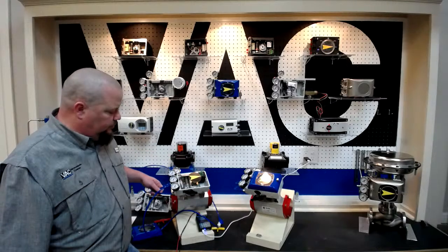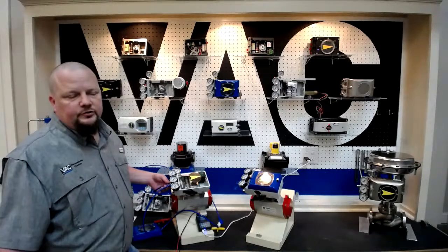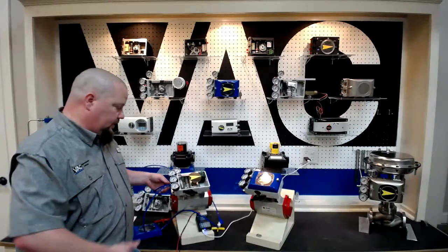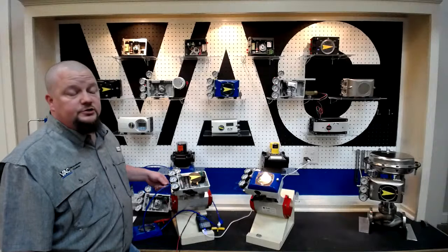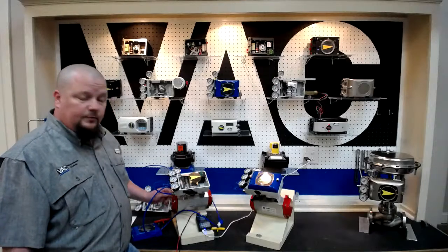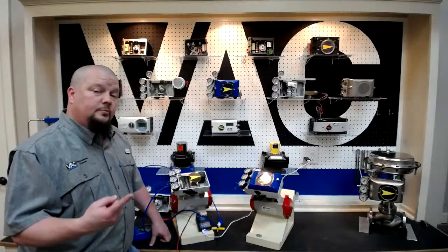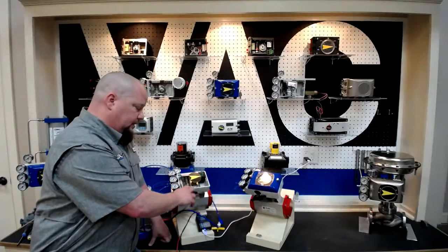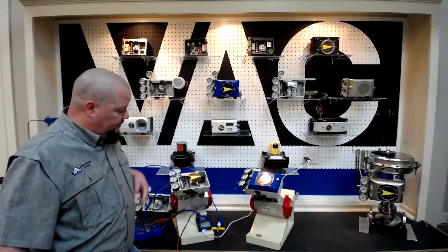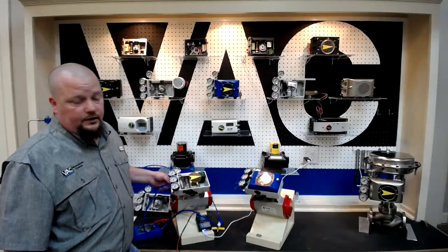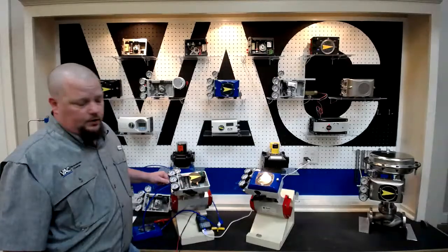Another issue is tubing. If you have a single acting actuator and you're hooking up the positioner, you have to make sure you're tubed properly. If you're tubing it single acting, which means one piece of tubing between the actuator and the positioner, you want to make sure that your second port is plugged and that you're using the correct port.